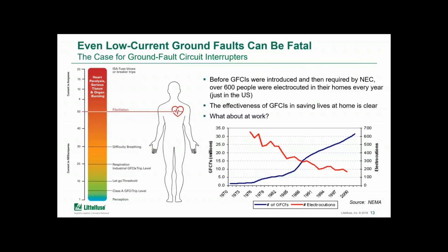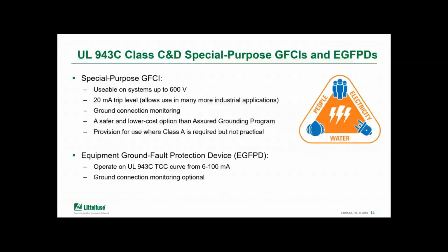Now, what UL has done in order to give a bit more flexibility to the industry is to go ahead and create a couple of new GFCI classes under UL 943C. And in the poll question there at the beginning, I see a few people have begun to hear about that. To explain what those are, Class C and D GFCIs trip at 20 milliamps. So this is something that's able to provide protection for personnel, but also gives a little more flexibility for those industrial applications. Those classes, which are for use up to 600 volts line to line, are referred to as special purpose GFCIs. So you might sometimes see SPGFCI listed in some article somewhere.